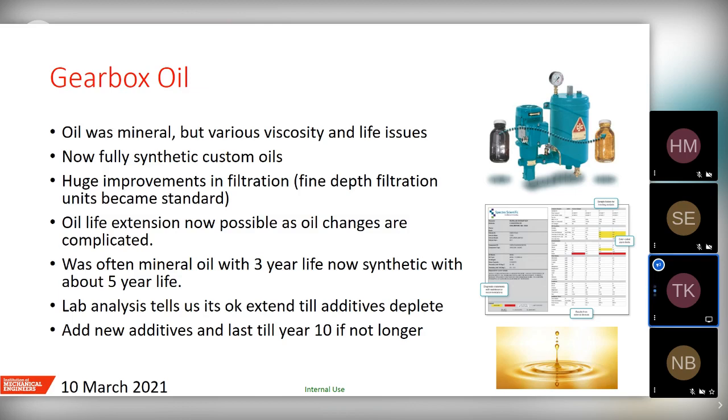So the best thing to do is either never change your oil, unfortunately that's a bit hard at the moment, or do it as minimally as possible. It used to be that you'd get, say, 3 years out of mineral oil, but now with synthetic, you normally get at least five. But we use oil analysis every year at least to see how the oils are going. And actually, most of the time, it says that after 5 years, oils are absolutely fine. But you will start seeing degradation of the additive packages.